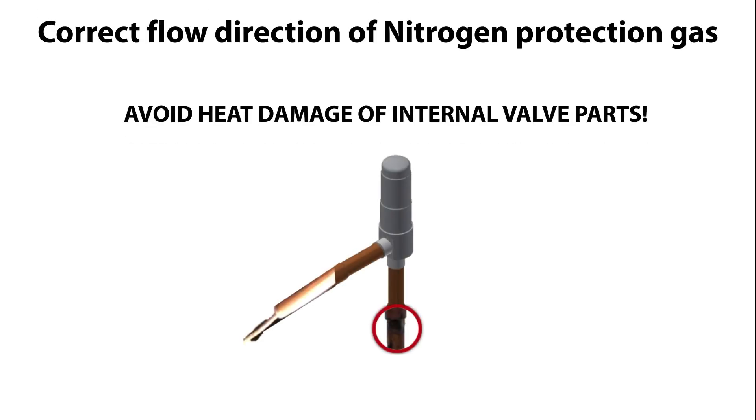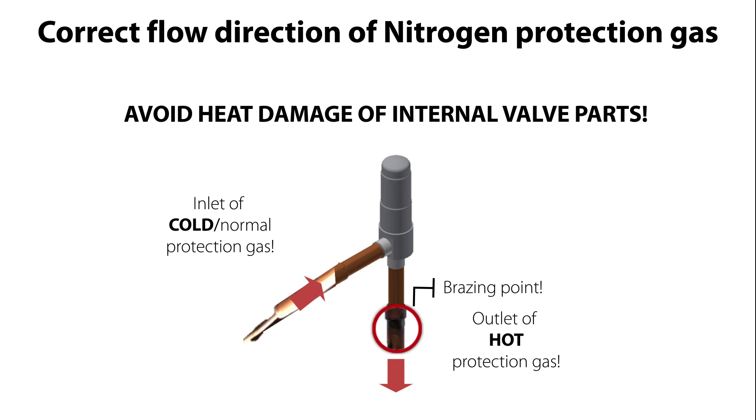This is very important because this flow direction ensures that the gas heated up during brazing flows away from the valve body and not into the valve body, which in such case might damage the internal valve parts.